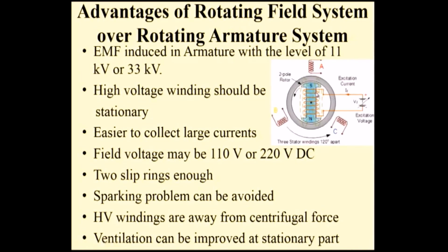Another important advantage: in a three-phase alternator, only two slip rings are needed if the field is rotating. If the armature were rotating, we would need three slip rings to collect electrical energy. With the rotating field, only two slip rings are needed — one for positive supply and one for negative supply — to provide DC to the field system. There is also less sparking problem: if the armature were revolving, you would have to collect 11,000 volts through the slip ring and brush assembly, causing sparking. With the rotating field carrying only 110–220 volts, the sparking problem is greatly reduced.